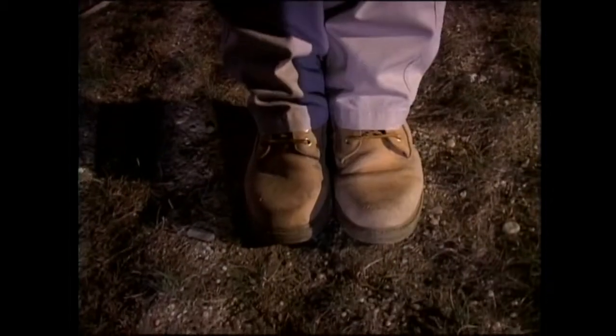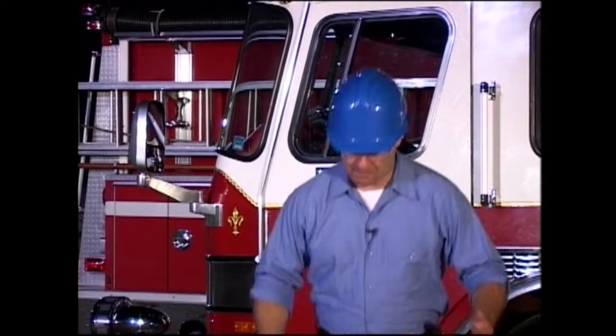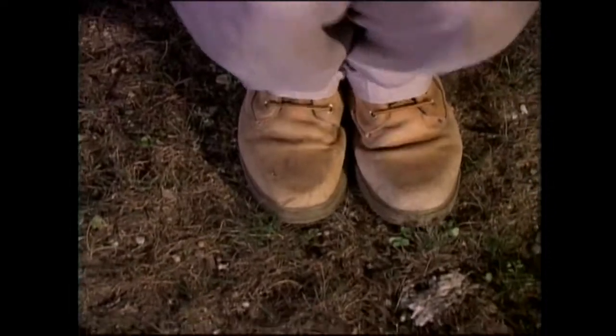To combat this danger, take very small shuffle steps with feet close together and always keep in contact with the ground. An alternative method of movement is to hop, taking very short hops with both feet together and making contact at the same time.